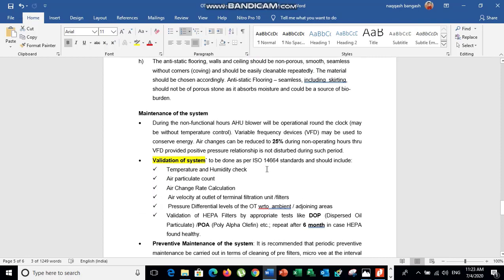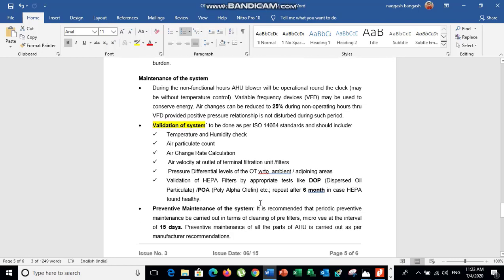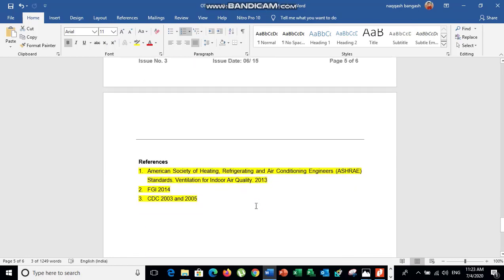Several tests should be carried out to verify that the OT is operating at the required parameters: humidity and temperature checks, particulate count, air change rate verification, HEPA DOP test, pressure differential test, and air velocity check. These tests should be performed every six months to confirm the system is maintained at standard parameters.